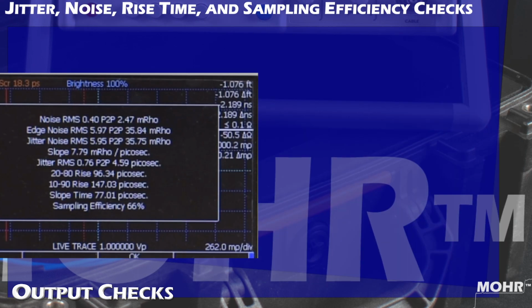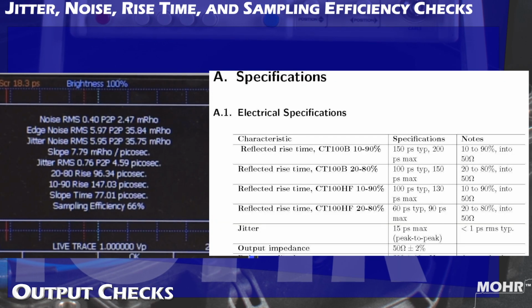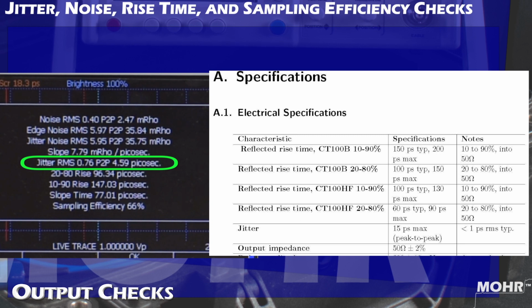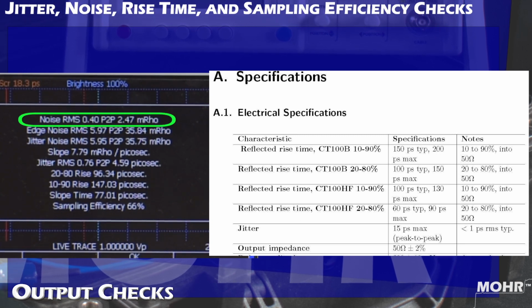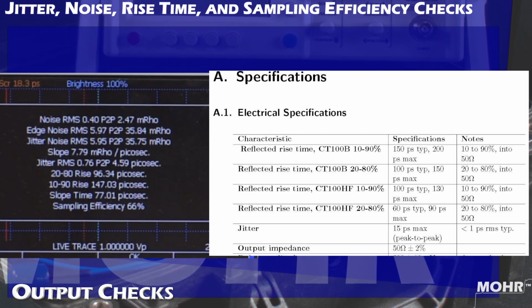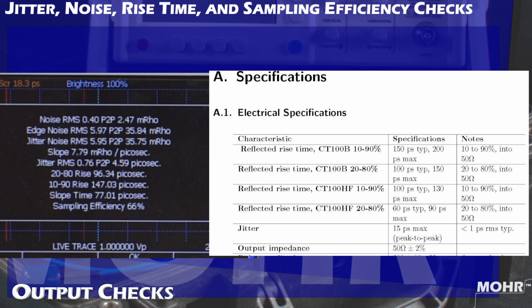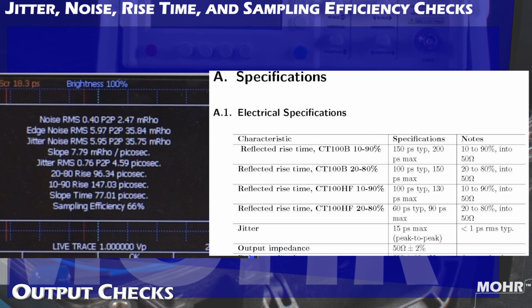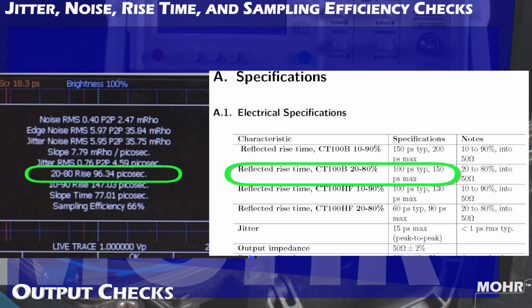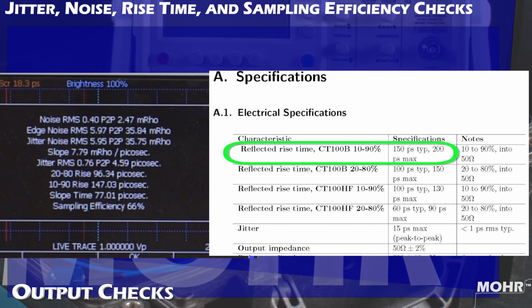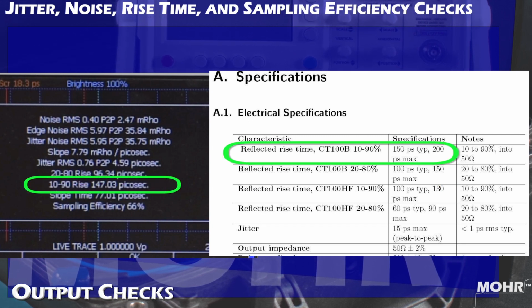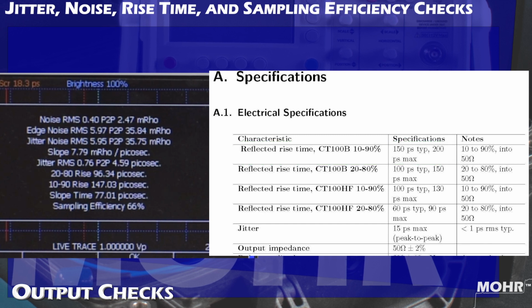The value for jitter used in the specification for a CT100B is jitter peak to peak. The value for noise is noise peak to peak. The value for 20 to 80% and 10 to 90% reflected rise times are both displayed as 20 to 80 rise and 10 to 90 rise, respectively, and can be compared with Appendix A specifications in the MOHR CT100B operator manual.